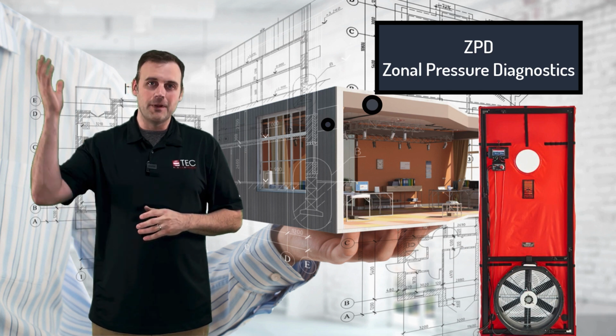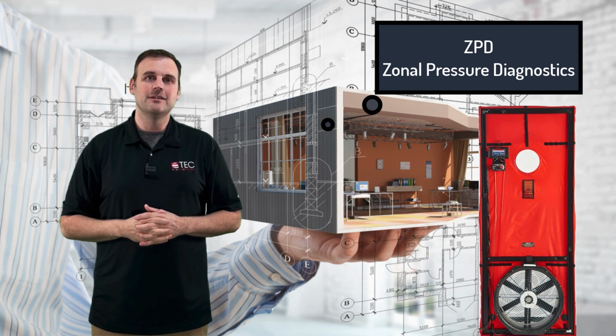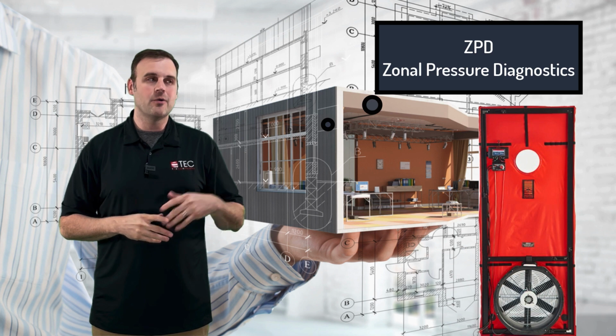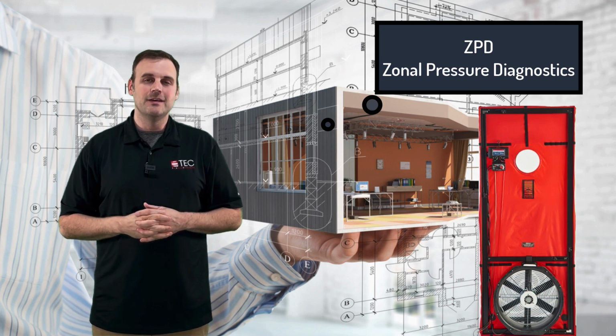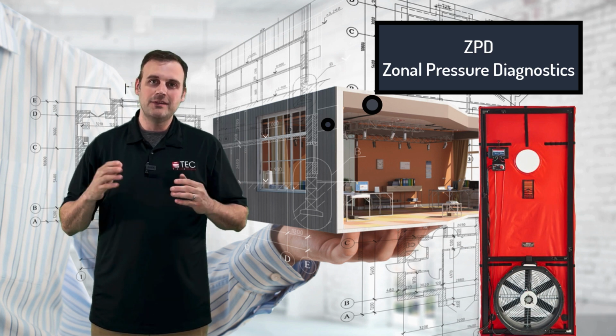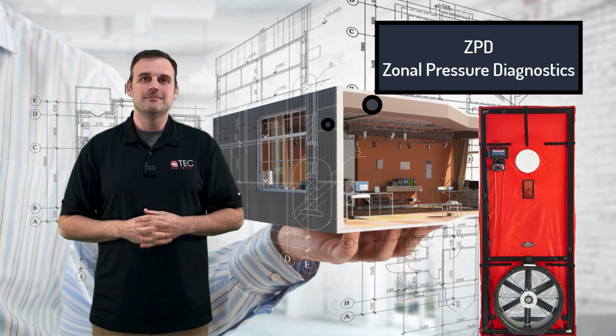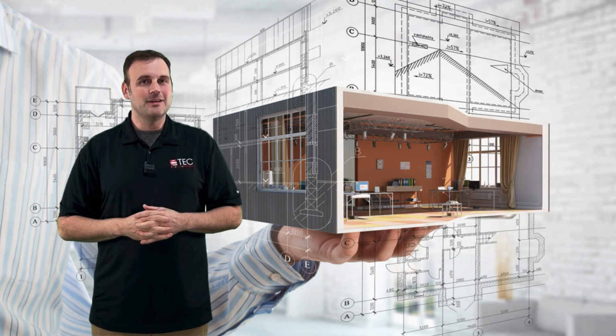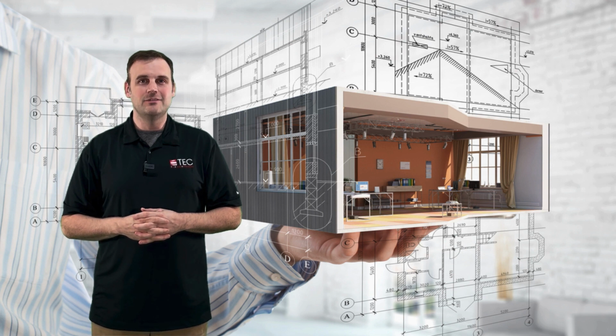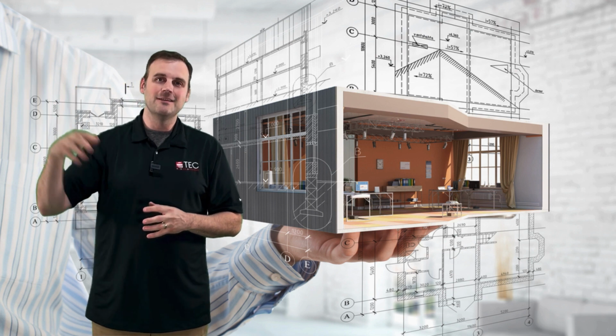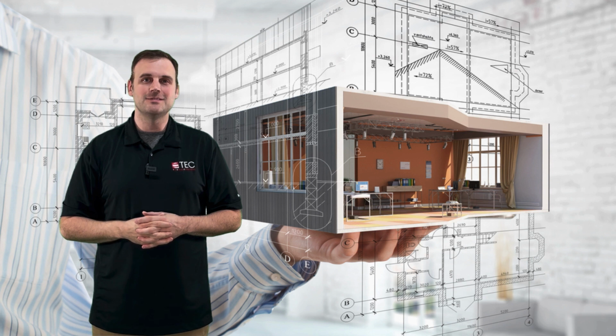I would then open the attic stairwell down that is inside the home, and I would run the blower door again. That would let me push more CFM through the attic. There's a lot more to it than that, but what we're trying to figure out during that test is to establish how much of the ceiling is part of the leakage.